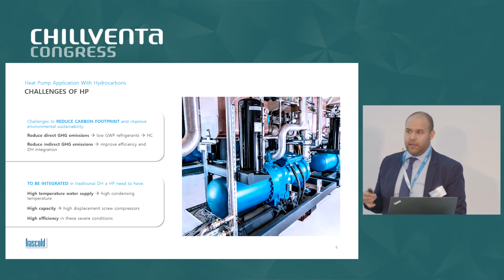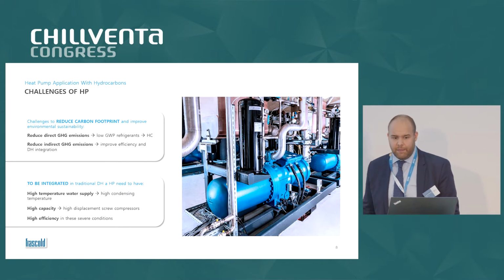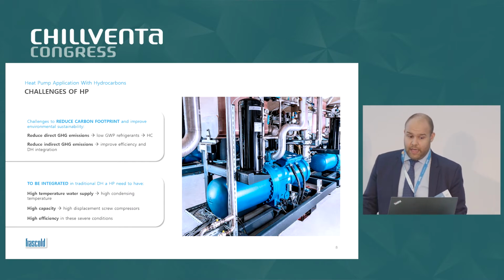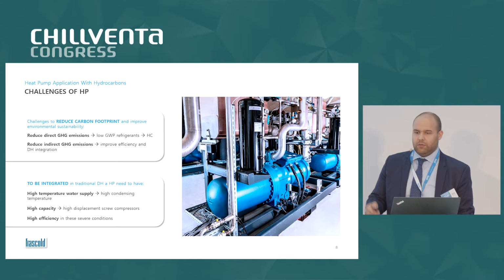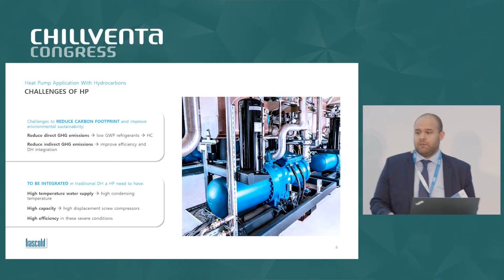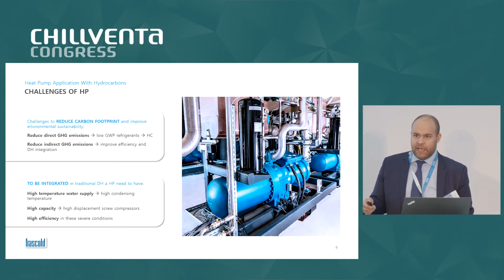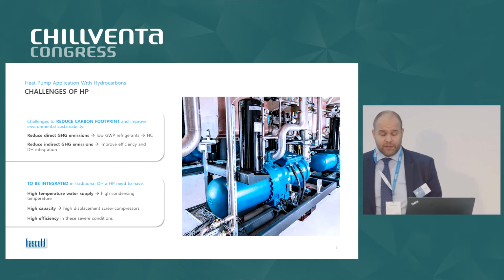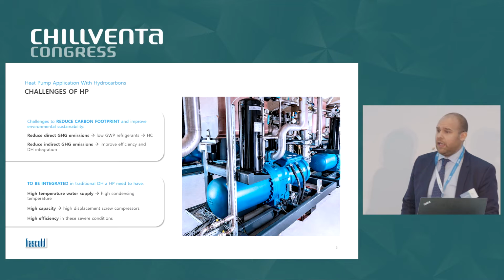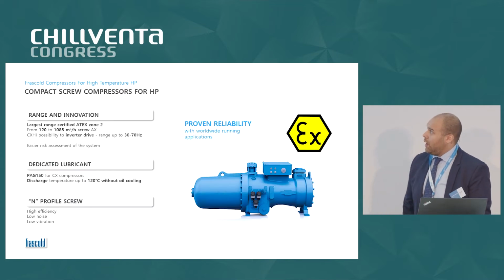To be integrated in a district heating system, heat pumps need high temperature water supply. So from the compressor point of view, this means high condensing temperature and high capacity. From the compressor point of view, high displacement, so screw compressors, and high efficiency in these severe conditions.